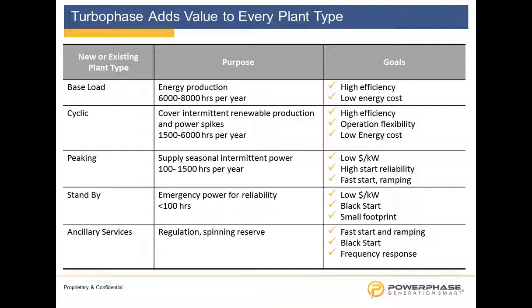In addition, then, as into the true peaking environments, those of you that run 2 hours every other week, just to support emergency needs or to backstop renewables, the challenge there is your start times. If Turbophase is applied to your combined cycle assets that run more and is literally not running, it is available to immediately bring on versus a 10-minute start simple cycle, say LM6000.